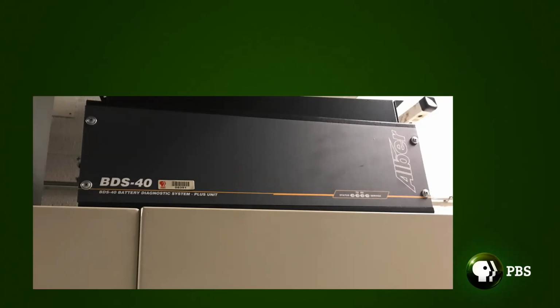This is one of a number of different manufacturers. This is an Alber, but there are 5 or 6 others. What these do, by using multiples of these, is monitor the health of every single battery individually. So you can see if you have 1 or 2 batteries in a string of, say, 20 that are starting to fail. That way you can maintain them or replace them before they become a significant problem. And that, once again, is thoughtful design.